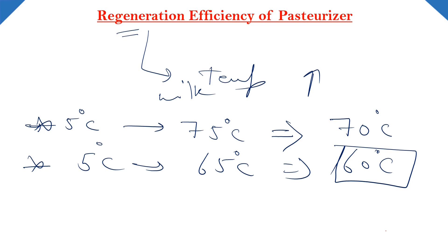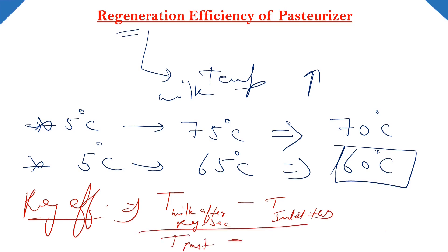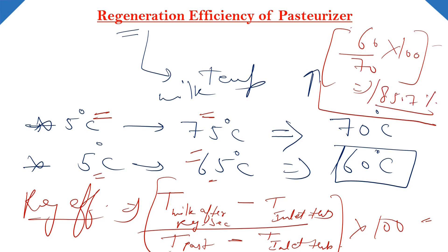Toh regeneration efficiency hamari kya hui? We calculate regeneration efficiency by one simple formula. Regeneration efficiency = (temperature of milk after regeneration section minus inlet temperature) divided by (pasteurization temperature minus inlet temperature of milk) multiplied by 100. So by using this relation, we can calculate the regeneration efficiency. That is: (65 - 5) divided by (75 - 5) multiplied by 100 = 60 divided by 70 multiplied by 100 = 85.7%. So that is the regeneration efficiency of the pasteurizer.